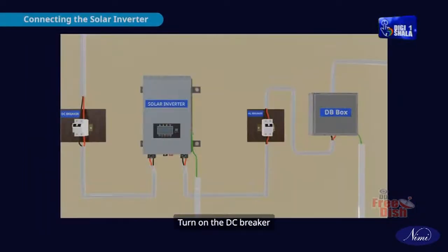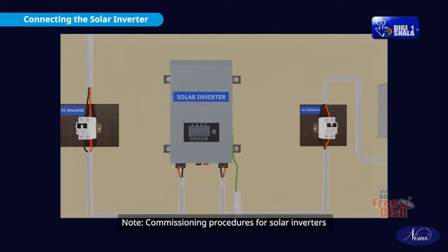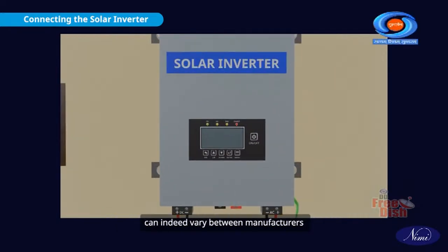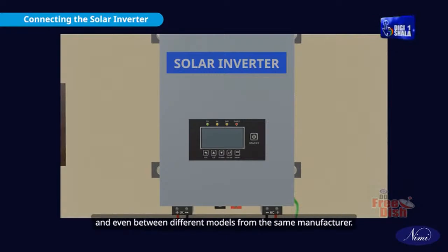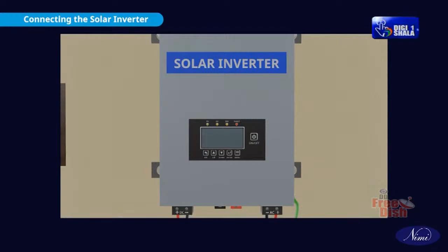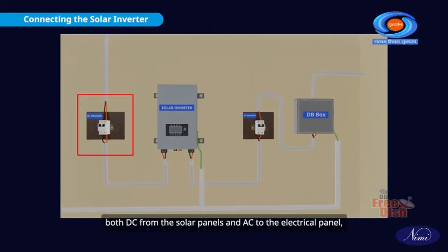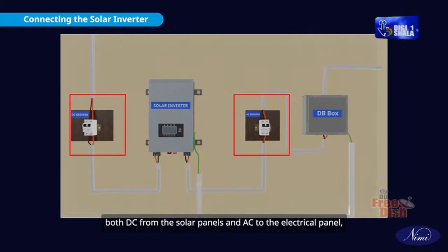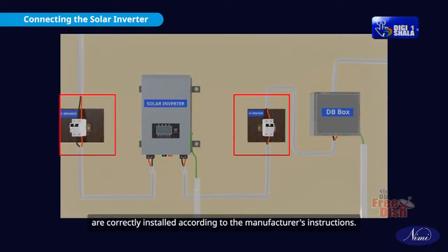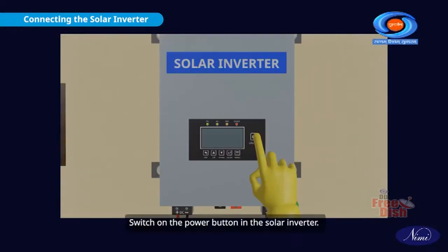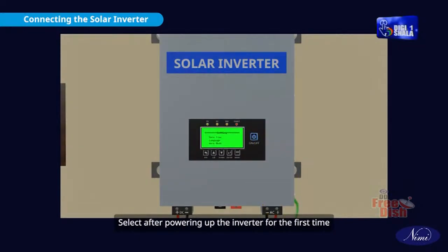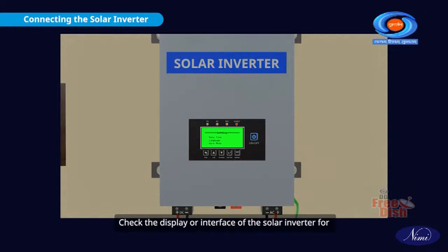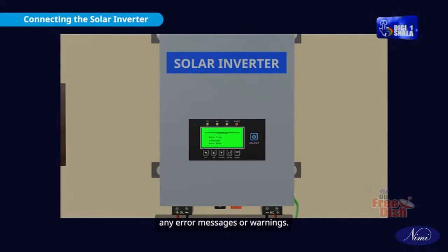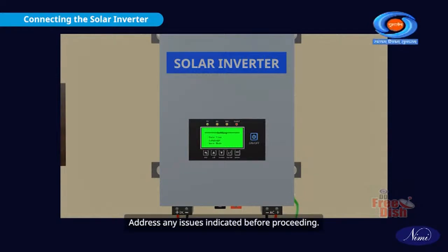Commissioning of solar inverter. Turn on the DC breaker. Note, commissioning procedures for solar inverters can indeed vary between manufacturers and even between different models from the same manufacturer. Verify that all wiring connections, both DC from the solar panels and AC to the electrical panel, are correctly installed according to the manufacturer's instructions. Switch on the power button on the solar inverter. After powering up the inverter for the first time, the language dialog is shown. Check the display or interface of the solar inverter for any error messages or warnings. Address any issues indicated before proceeding.